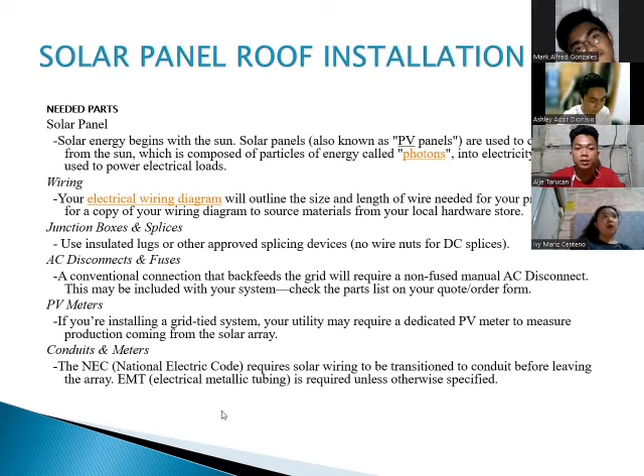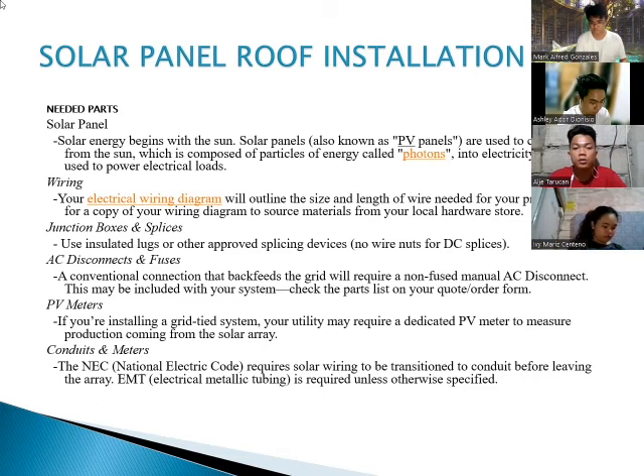The next is the wiring. Kailangan din natin siya para yung electrical wiring diagram will outline the size and length of wire needed for your project. As for the copy of your wiring diagram, source materials from your local hardware stores. Then next is the junction boxes and splices. Use insulated lugs or other approved splicing device, or no wire nuts for DC splices. The next is AC disconnect fuses. A conventional connection that backfeeds the grid will require a non-fuse manual AC disconnect. This may be included with your system. Check the parts list on your quote and order forms.